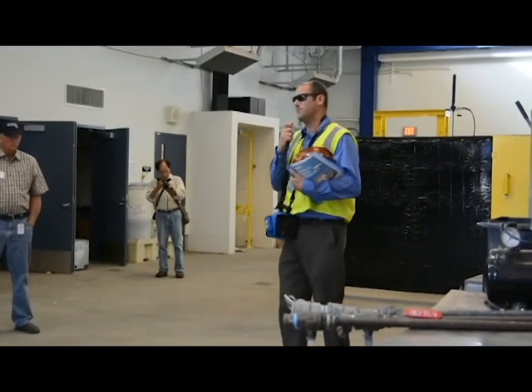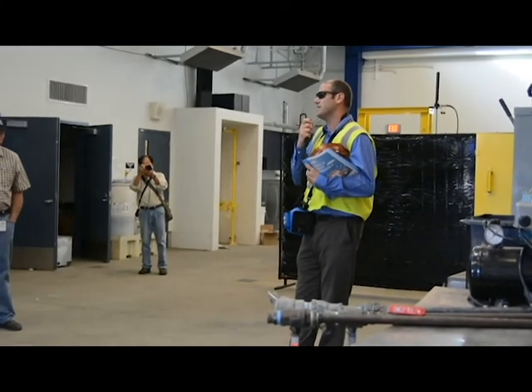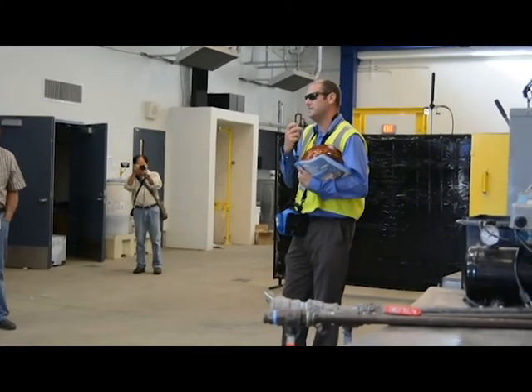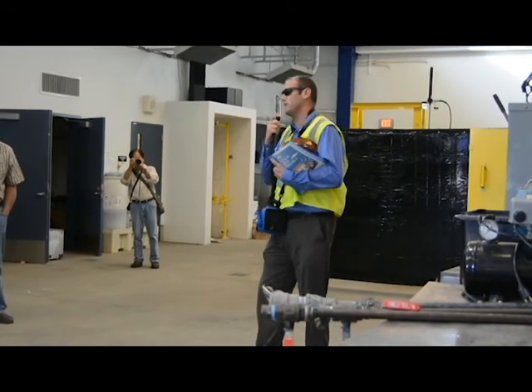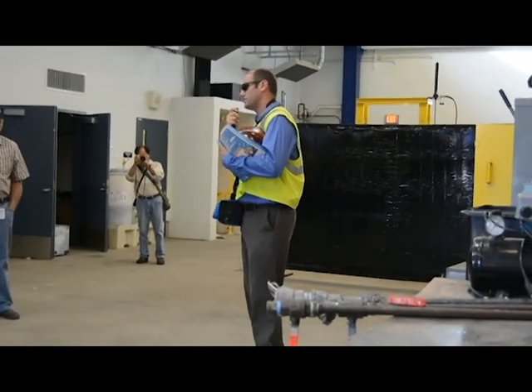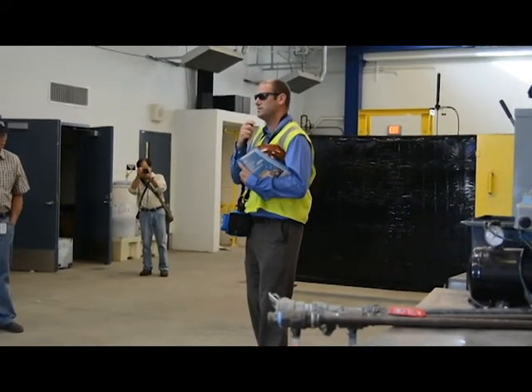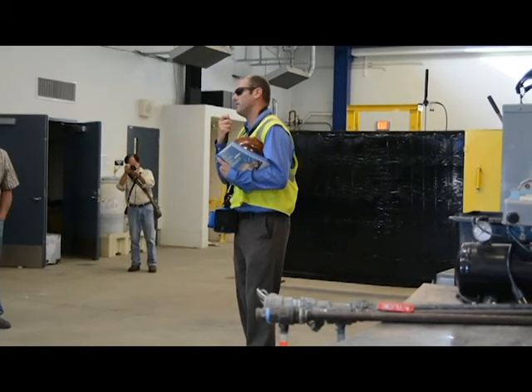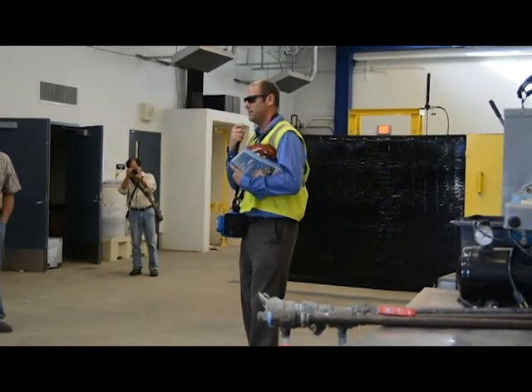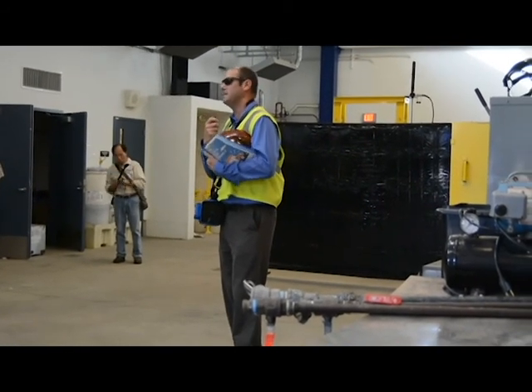We operate 3 different systems: a drainage collection system, and we have a first flush system that takes the drainage water and sends it to 10 million gallons of storage on the airfield. That gets diverted into our industrial plant. So although we're treating anywhere from 300,000 to 700,000 gallons a day on our industrial side, that will go up to about 1.7 million in wet weather as we bring in all that first flush. We're trying to get the rubber from the tires on the airfield and things like that into this system.